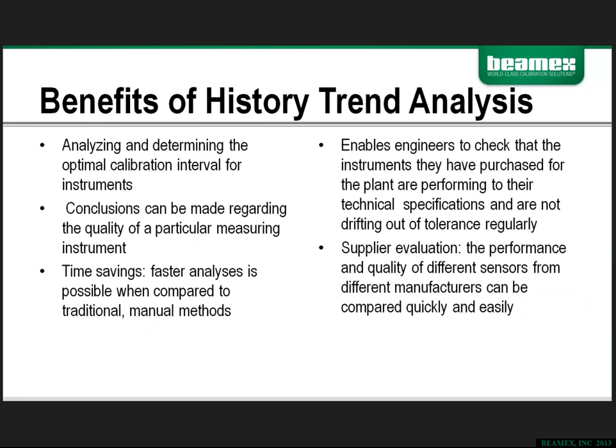Some of the benefits of running a history trend analysis are as follows. The information that's provided makes the analysis easy for determining the optimum calibration interval. And you may ask why that's important. Well, given that you have, in some cases, thousands of tags or positions that you have to calibrate annually, if you were able to adjust those calibration intervals based on performance, and over time you were able to eliminate some of those actions that you would normally do, say, every 6 months, you're not only going to save time, it's going to allow you to do other maintenance activities or stay more current on your existing calibrations.